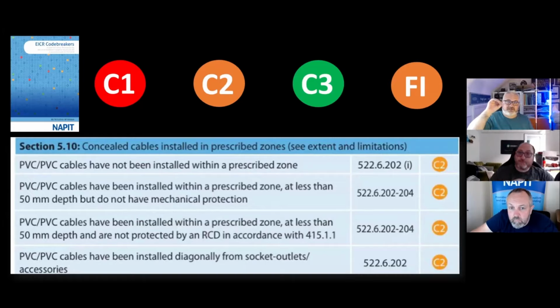The reason I say that is because of what we now know about RCDs, the installation and mutual interaction with the fixed electrical installation, especially with Type AC. I can't hand on heart say if there's a solar PV array and an EV charger going, that RCD is actually going to do anything anyway. So I'll be C3ing the RCD, never mind whether the cables are buried at the right depth. But the regulation requires additional protection under 415.1. Yeah, I know.